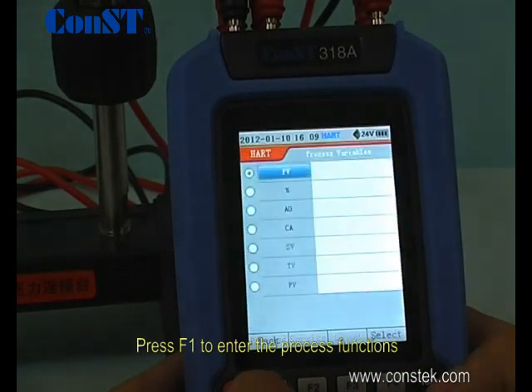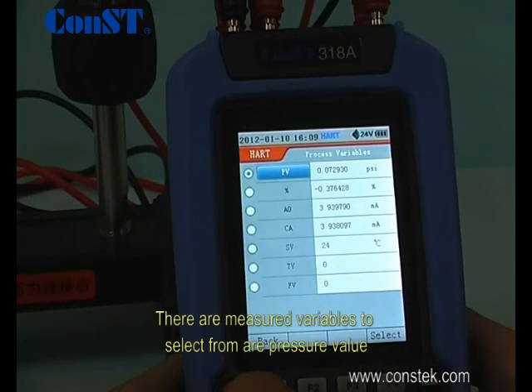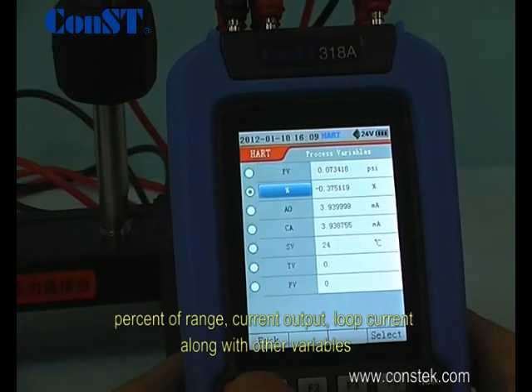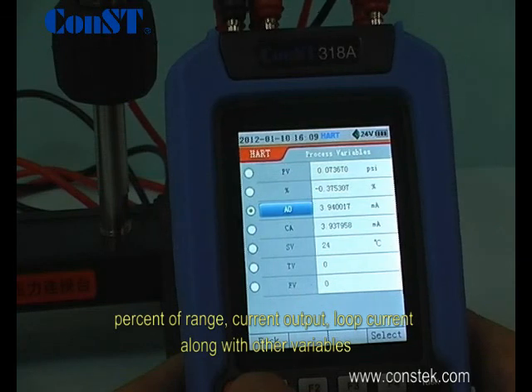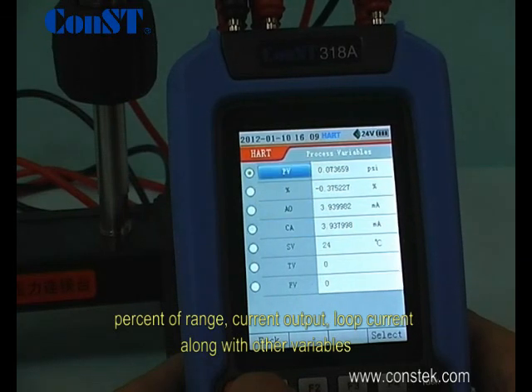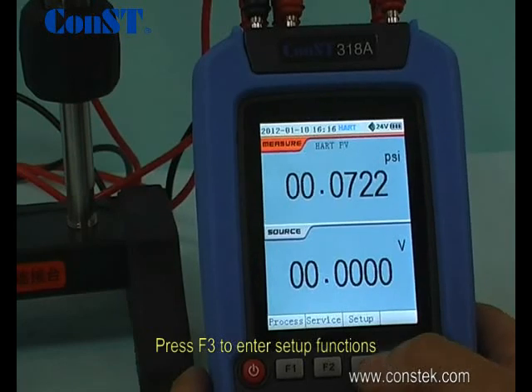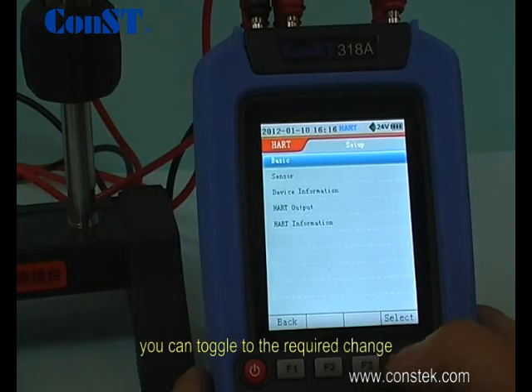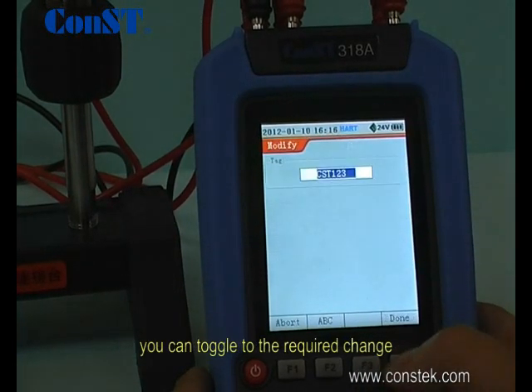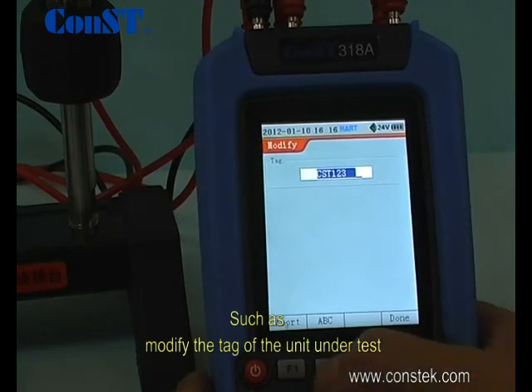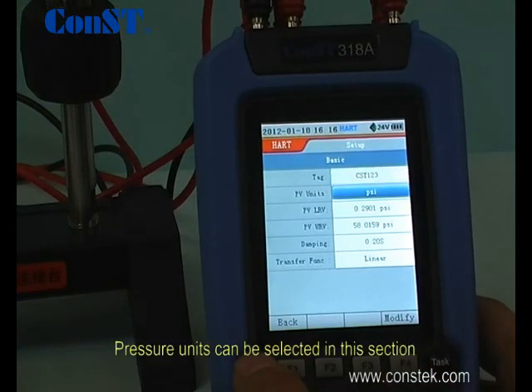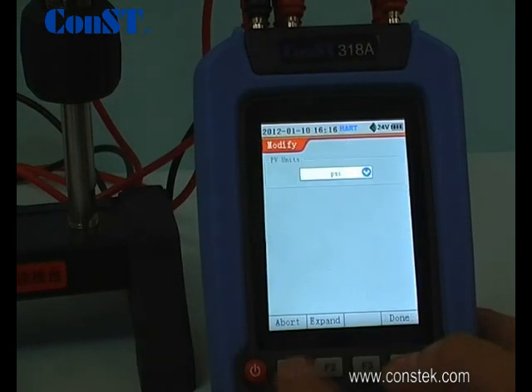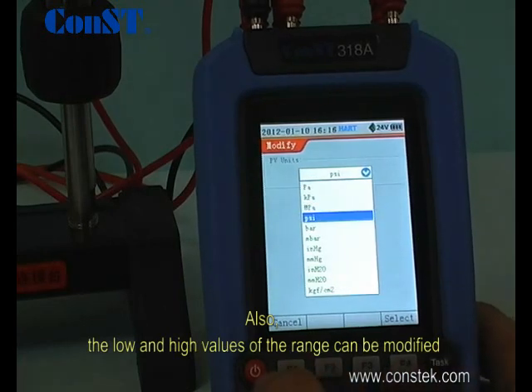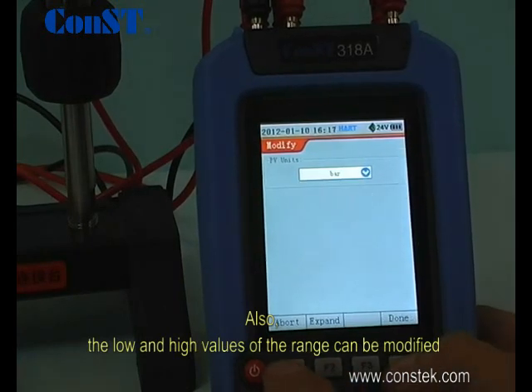Press F1 to enter the process functions. The measured variables from which to select are pressure value, percent of range, current output, loop current, along with other variables. Press F3 to enter setup functions. You can toggle to the required change, such as modifying the tag of the unit under test. Pressure units can be selected in this section. Also, the low and high values of the range can be modified.